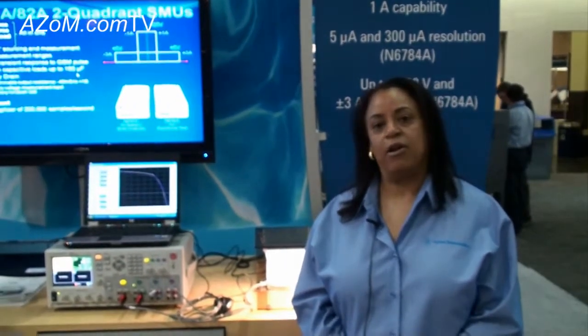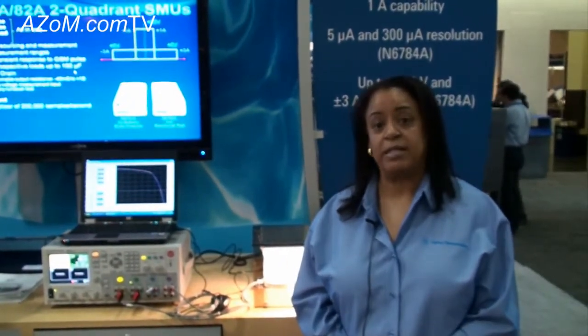What a source measurement unit does is it's basically a precision power supply that can source very precisely and also measure very precisely, so low signals can be accurately tested.